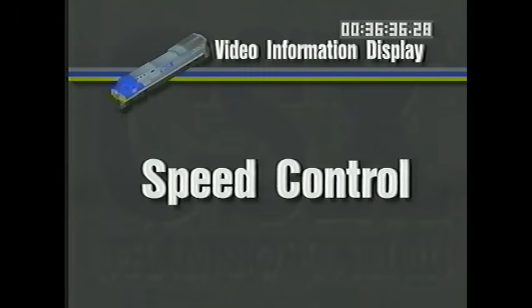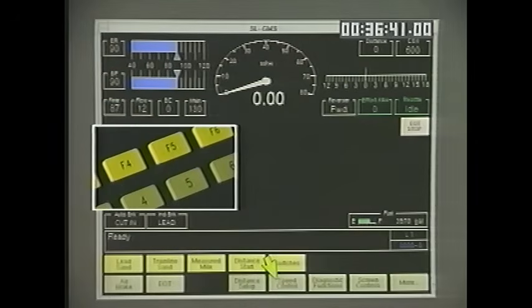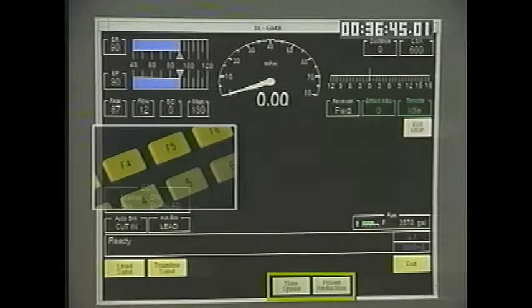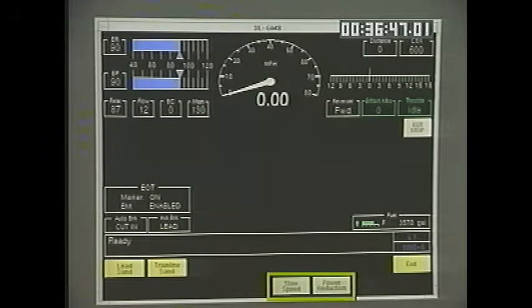To access speed control and power reduction features, you must press 5 from the main menu of the operating display. 2 additional menu choices appear. They are slow speed and power reduction. Slow speed allows you to set the slow speed control. Power reduction provides access to the manual power reduction mode. We'll begin with a look at how to set the slow speed control.